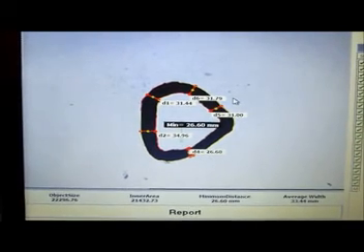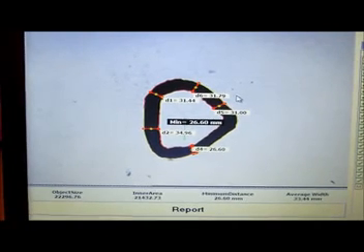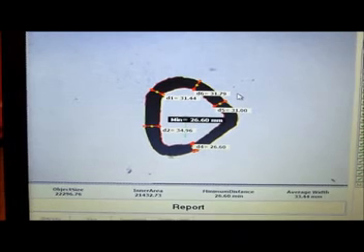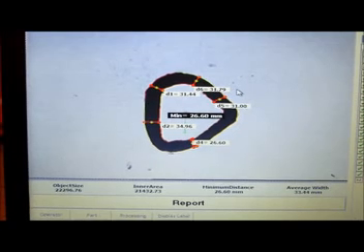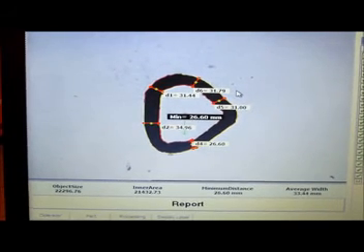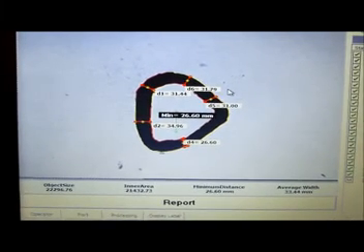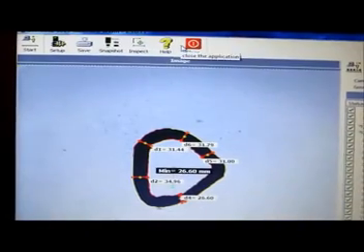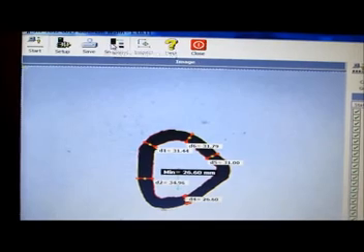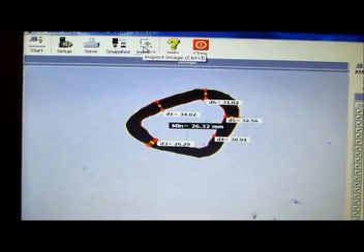We can do the programming for XLPE cable sample. Plus we have optional modules like color identification, which is for calculating the yellow and green percentage in the cable. And then we have the XLPE transparency measurement module for tree identification and tree formation analysis. So this is a very user-friendly software for cable measurements. What the operator has to do is just a simple snapshot and inspect. Keep the component in any orientation, you change the orientation, press snapshot. You can change the position and the orientation both, press snapshot and inspect.